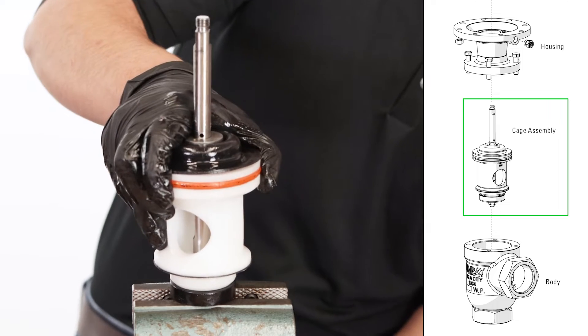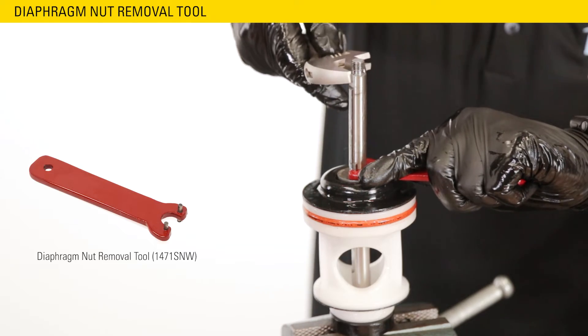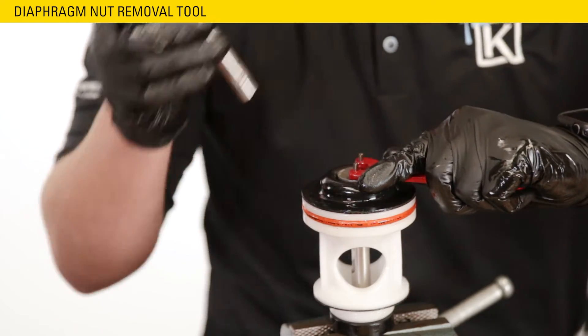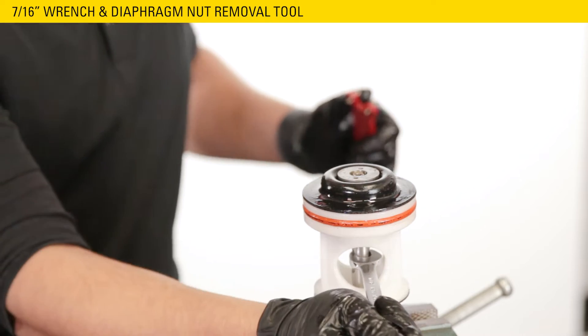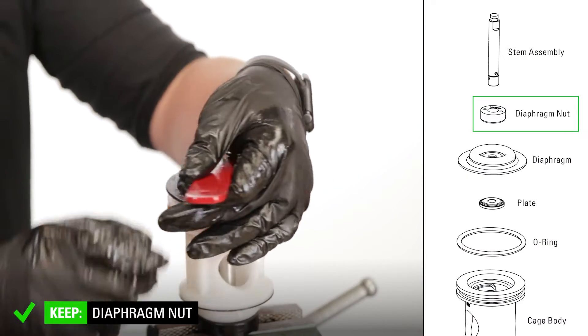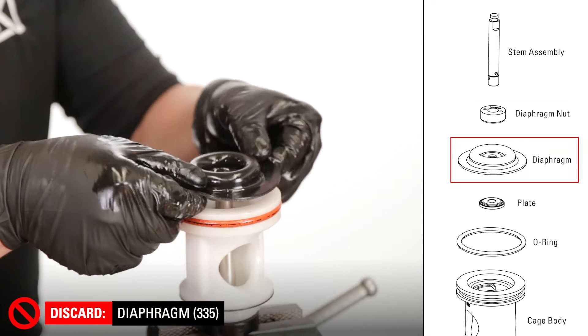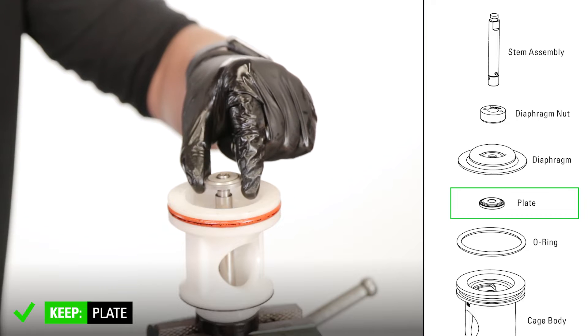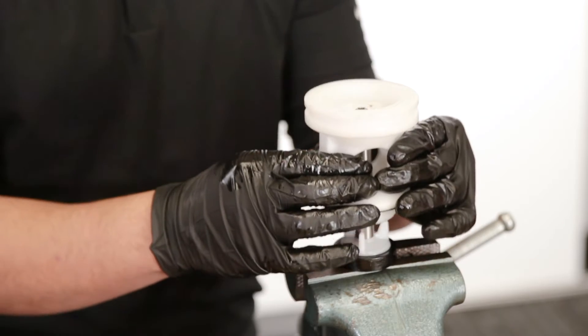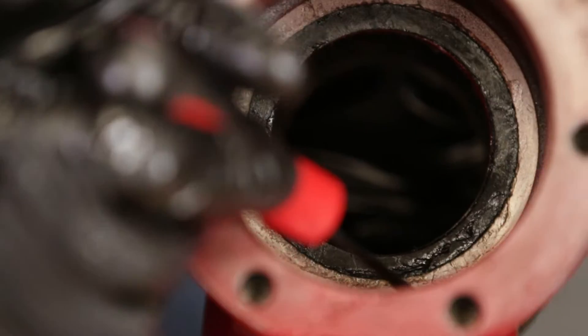Secure the cage assembly in the vise by the lock nut. Use a spanner wrench or Kimray diaphragm nut removal tool to hold the diaphragm nut still while you unthread the stem assembly with an adjustable wrench. Put a 7/16ths wrench on the flats of the stem and remove the diaphragm nut with the Kimray tool. Remove and discard the diaphragm, then remove the plate and set it aside. Use a pick to remove and discard the large O-ring around the cage, then remove the cage from the stem. Remove and discard the gasket from the bottom of the cage — this could also be stuck inside the valve.